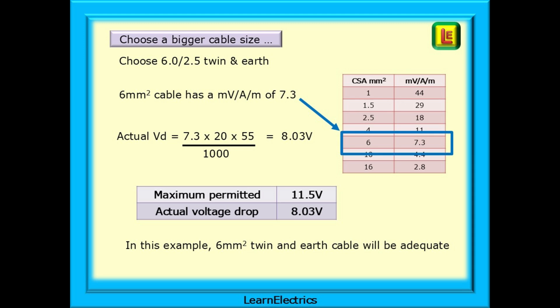What happens if we choose a bigger cable size, ignoring the fact that it costs more money? If we choose 6x2.5 twin and earth, the table tells us the 6mm cable has an MVAM number of 7.3. If we put this number into the calculation, we have a voltage drop of just 8.03 volts. Perfectly acceptable. The maximum permitted voltage drop is 11.5 volts and the actual voltage drop is just over 8 volts. In this example, 6mm twin and earth cable will be adequate.